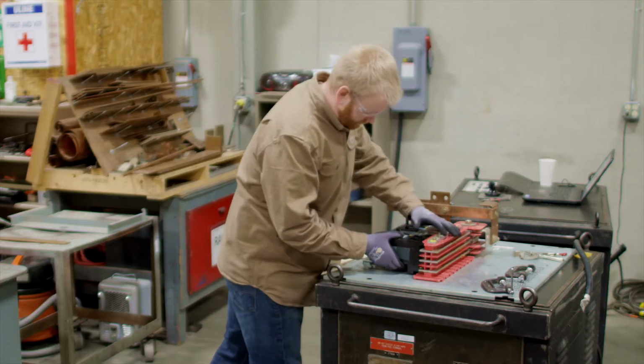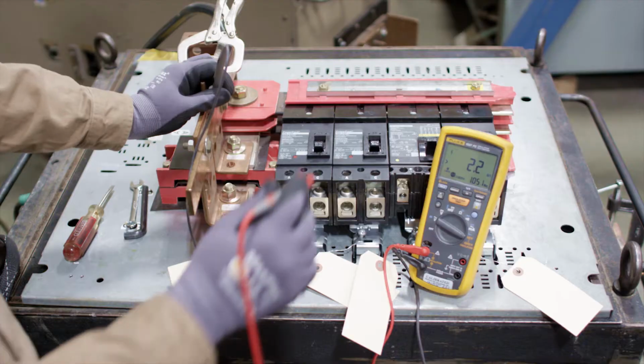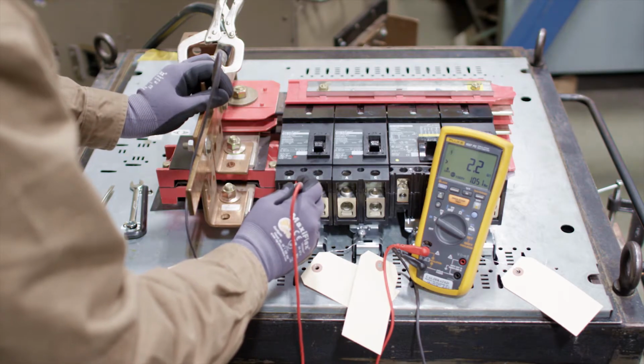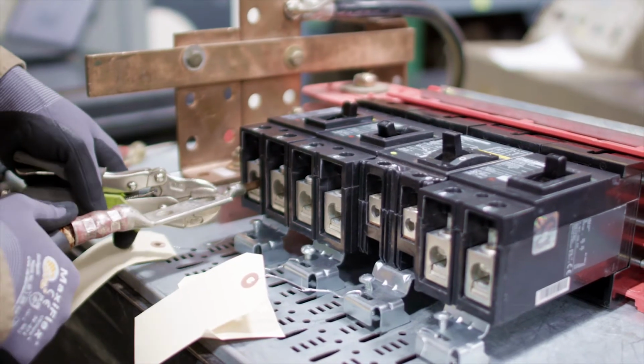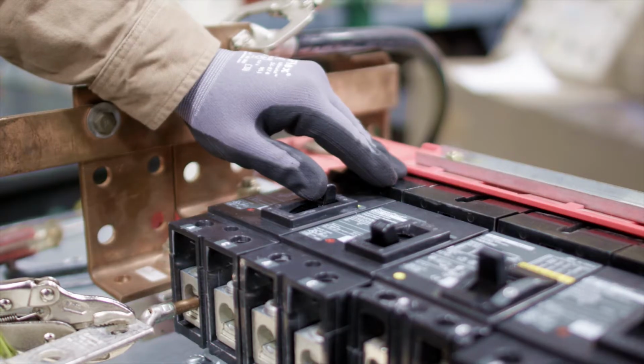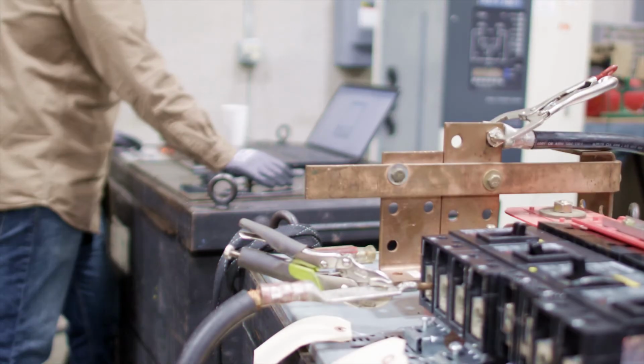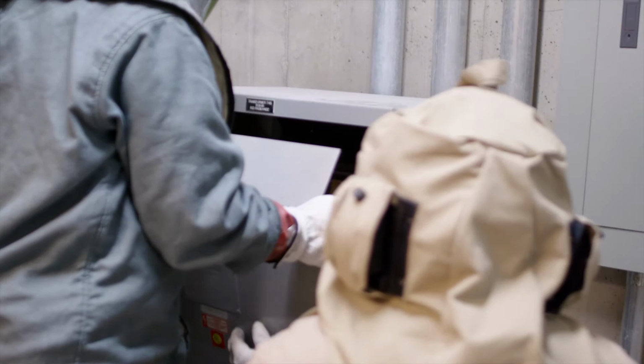Next you want to test the insulation, which is the ability for the electricity to stay inside the gear. Then measure how well the circuit breaker reacts as far as timing goes: long time, short time, instantaneous. And you want to measure the integrity of your transformer, which gives you an idea of how long your system's going to last.